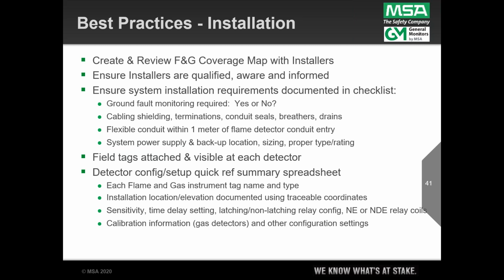I want field tags visible for my operators and my maintenance people. And I'm going to make sure we've got a quick reference spreadsheet where I've got tags listed, installation locations, documented, traceable coordinates. I talked about that. Sensitivity, all the config settings: time delay, sensitivity, latching, cal gas. What kind? Is this a methane sensor or a propane sensor?